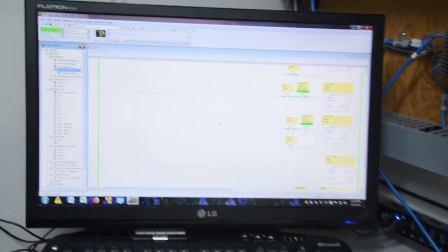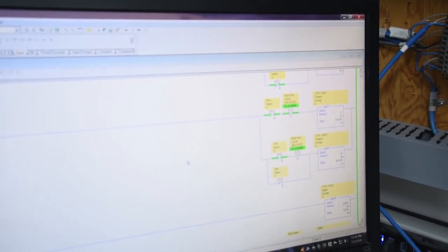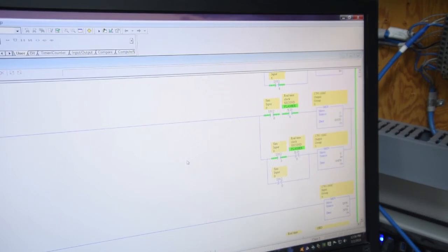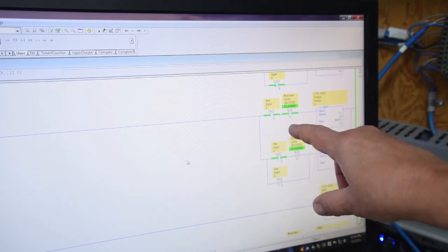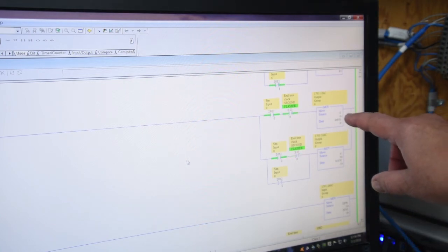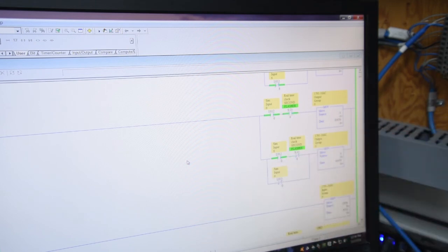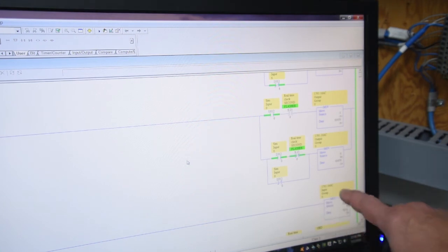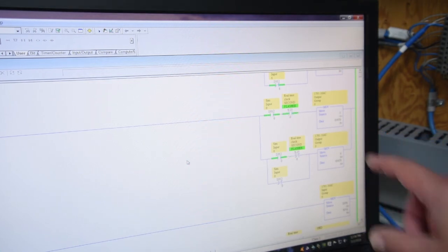So now we'll just swing around here to our computer screen and there is our really simple logic. It is input on one second flasher, which is S2 3.0, which is right from the time clock built into the PLC. Move minus one, which is everything on. When it's in the opposite state, move zero. And down here, we get to see that all of our inputs are going on and off matching everything here. So that's how simple these things are to test.